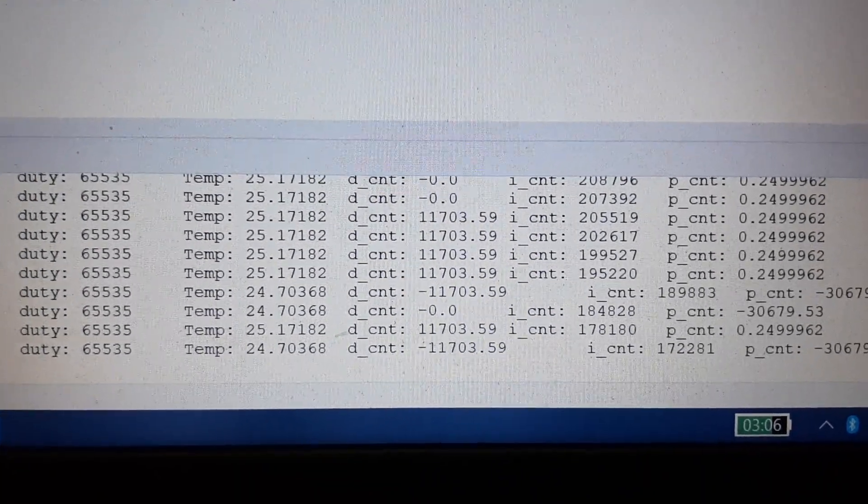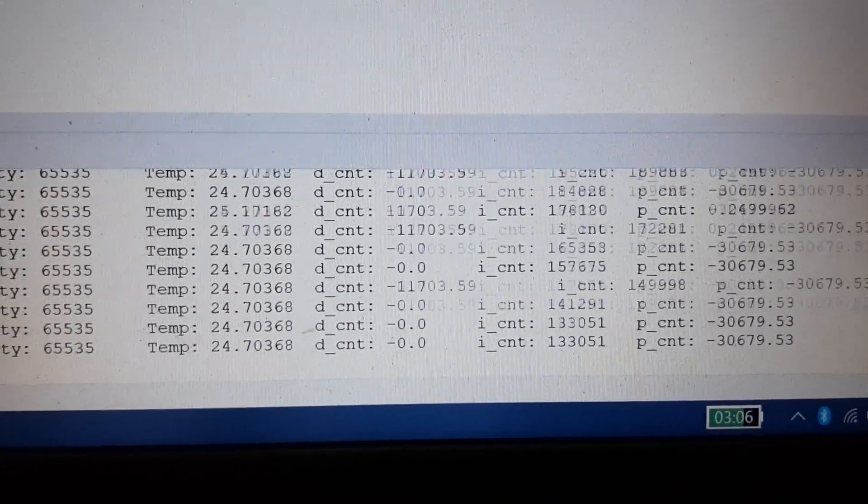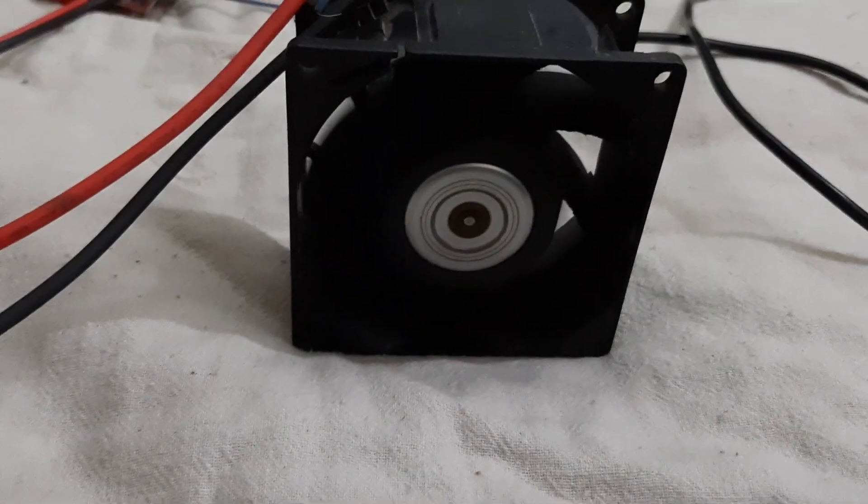The temperature is now 25.5 and the values of integral control are also dropping. You can see the proportional control is negative 30,000. You can see the fan is now stopped.